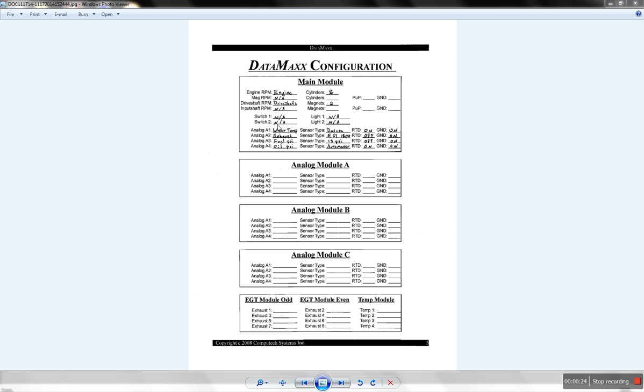So the first thing we want to do is fill out our actual configuration sheet. Engine RPM, drive shaft RPM, and analog A1, we physically have installed the water temp sensor, and analog A2 we physically have installed the exhaust gas temperature sensor, and A3 we have fuel pressure, and in A4 we have oil pressure. We referred to the instruction manuals to put down what type of sensor it should be listed as, as well as whether the RTD and the ground dip switches should be on or off.